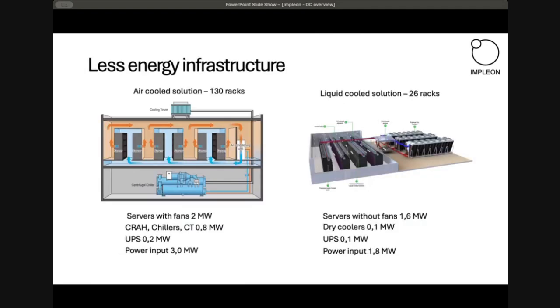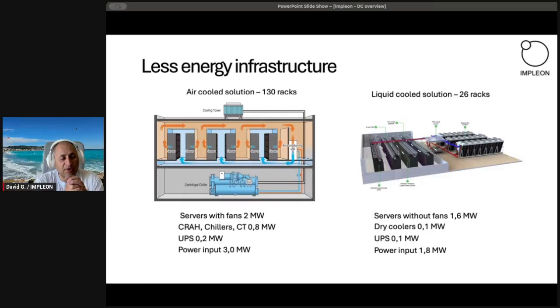If we look comprehensively at this transition from the point of view of facility-side energy consumption, we need much less energy infrastructure, and this is why. The first thing is that we will have the same compute, the same CPU and GPU power. So compute power is the same, and we compare apples to apples, but we will need much less racks, 26 instead of 130. The IT load also goes down, because we take away the fans and the temperature rises, so the IT power load goes down. This is why there is 8 times less energy consumption for the heat transfer infrastructure. On top of that, we should provide uninterruptible power supply, and that also goes down. So overall, we have 1.8 megawatt power input instead of 3 megawatt.